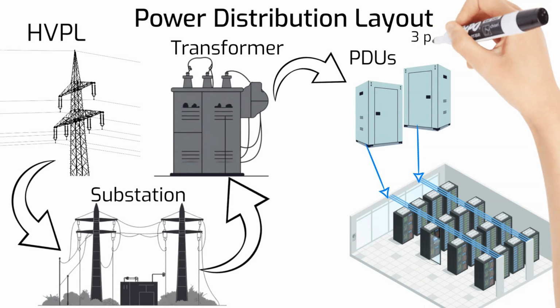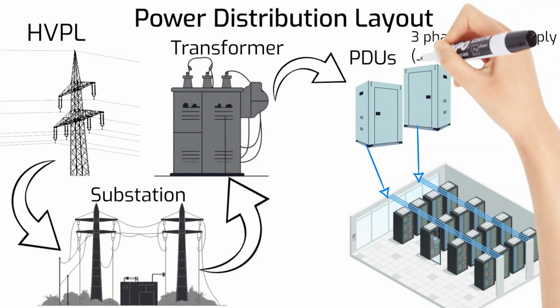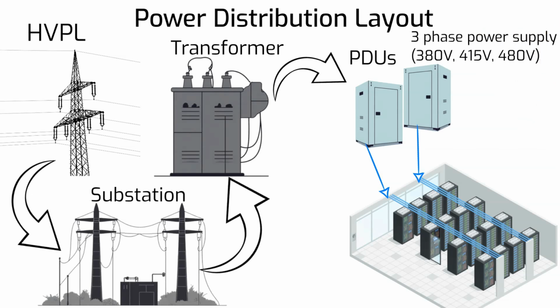Electricity enters the facility at high voltage and is distributed through power distribution units to each rack. Commercial mining operations overwhelmingly prefer a symmetrical three-phase power supply, e.g., 380 volts or 415 volts to 480 volts, for rack power, as it allows for better load balancing and saves on cable investment compared to 220-volt single-phase systems. High amperage PDUs, like 335 amp at 415-volt input, are used within the racks to deliver power directly to the miners. To ensure an efficient and stable system, the number of mining machines on each rack layer should ideally be a multiple of 3 to balance the current across the 3 phases.